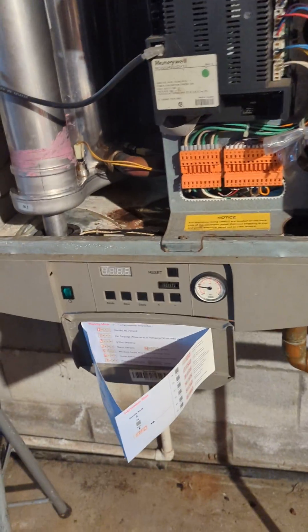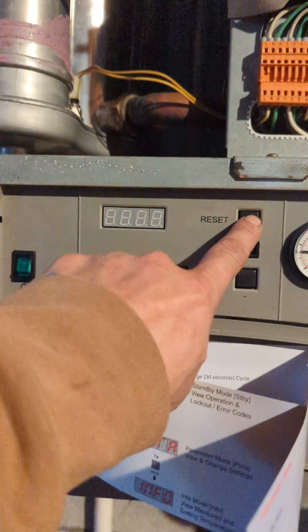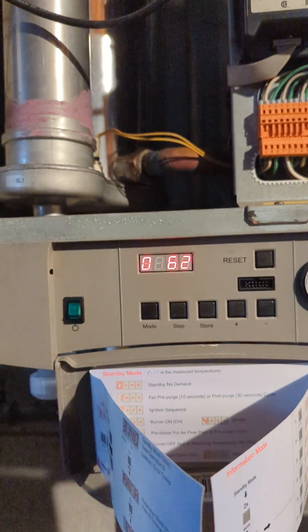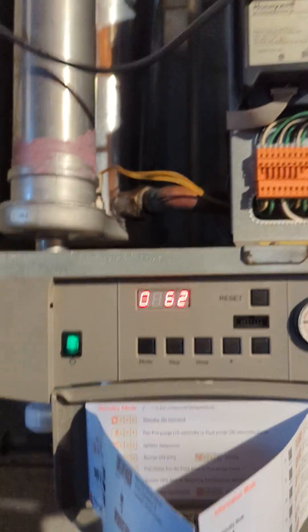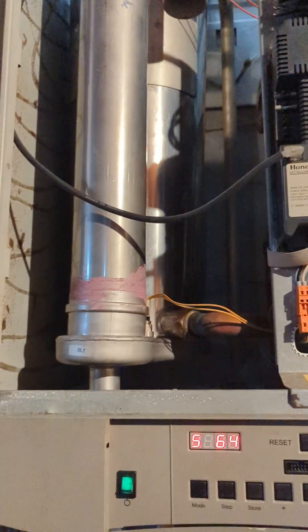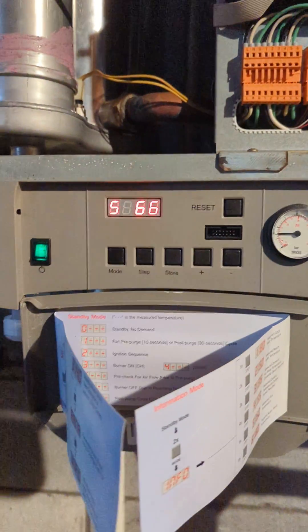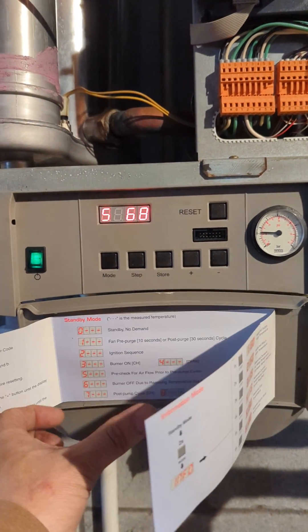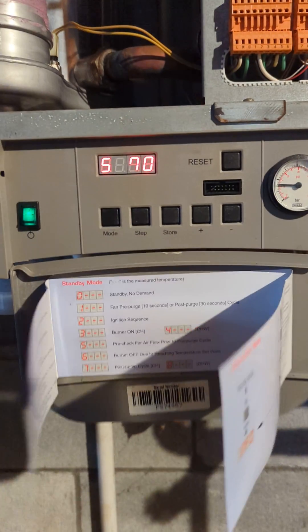This is the cover — it's the oldest model, the MCBA control board. We test it before doing anything else. It was locking out when you shut it off, so let's try it again. I tried to keep the ignition cable from touching the stainless steel.